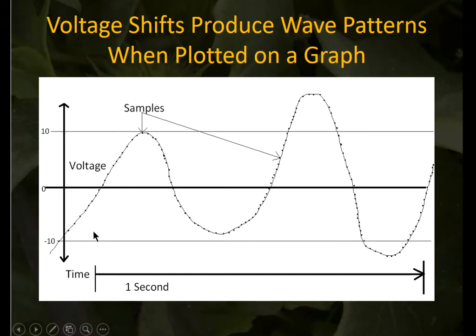Now, when we measure this activity on the scalp surface, we're actually measuring the voltage at any given moment between the active sensor and the system reference or ground. The term ground is a little bit misleading because it isn't actually attached to the ground, but it's usually called the system reference, which means it's the reference that the other electrodes are compared to.